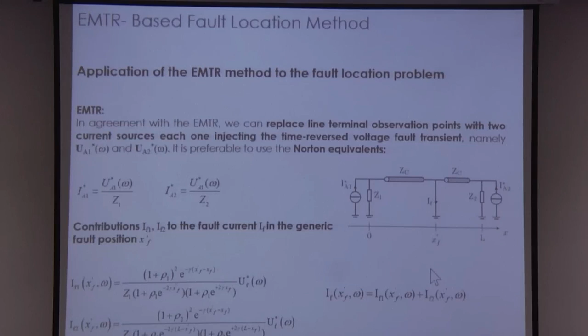This is an example: the line is 10 kilometers, and I apply a fault at 8 kilometers. In the first scenario, I record the waves at both ends. This figure shows the energy of the fault current as a function of guessed location. As we expect, at 8 kilometers we have a peak, which is our fault point.